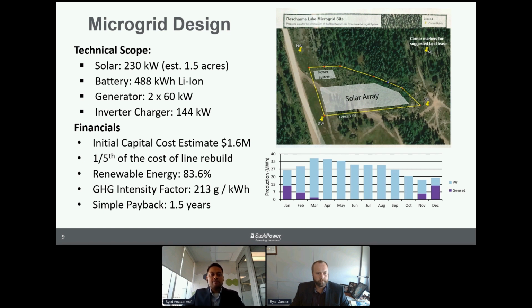That's why we decided on 2 gen sets in the system. So these are the specs of the microgrid we're going to proceed with: 230 kilowatts of solar, 488 kilowatt-hour lithium ion batteries, and 2 gen sets. So there's always a backup to the backup, basically. We don't want customers without power in any situation. The inverter charger's about 144 kilowatts.